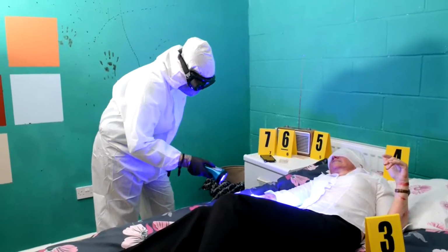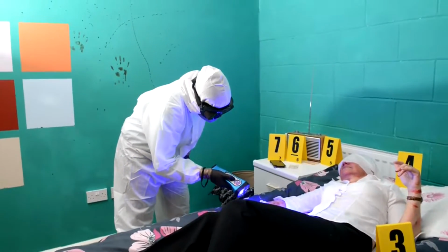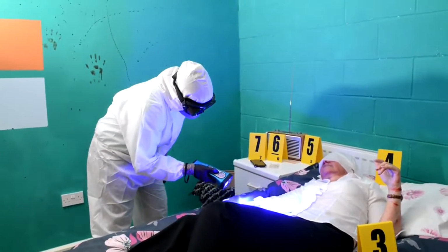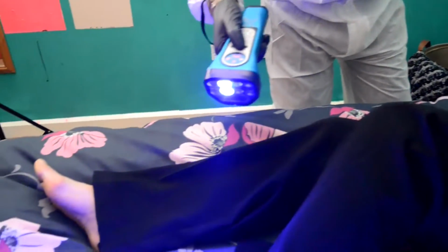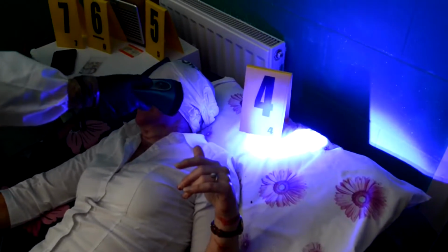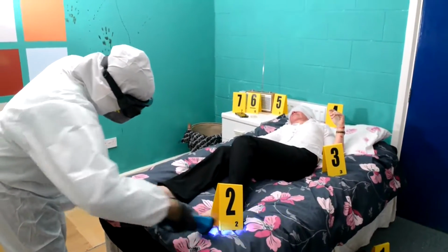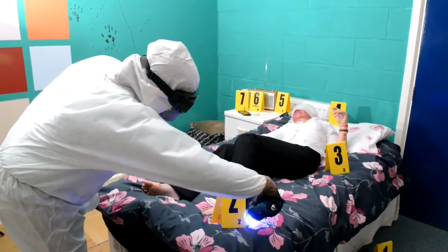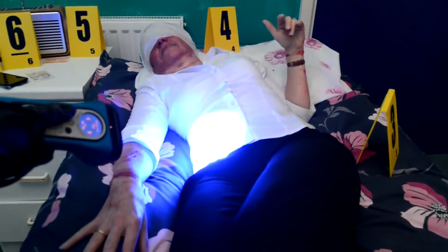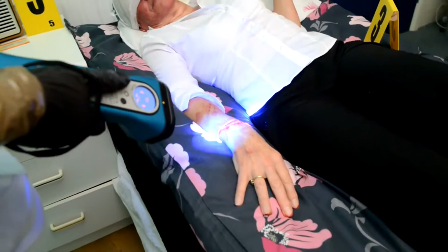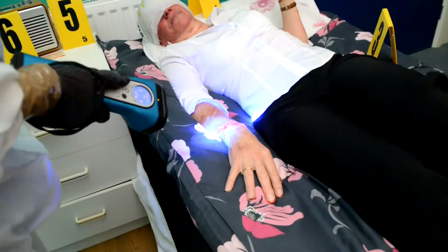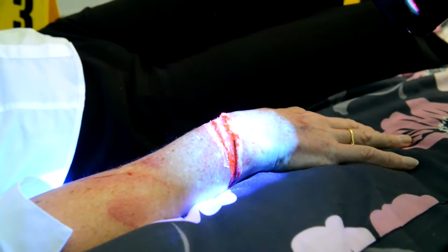As a serology light source, the X5 can reveal minute traces of body fluids, including semen, saliva, urine and vaginal fluids. This is achieved by performing a fluorescence examination, exposing the evidence to intense narrowband illumination at one wavelength and causing it to emit fluorescence at a higher wavelength. By wearing viewing goggles that filter out the illumination wavelength, we can view only the fluorescence to reveal evidence as a bright, high contrast stain.